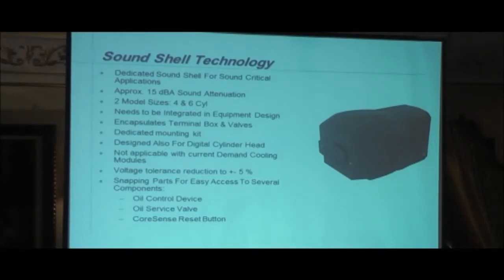Over and above that, we also offer now sound shell technology. It's basically a foam that's been molded, and that can be applied to fit around the compressor. So even with the redesign, we've had the reduction in noise. By using the sound shell, we're able to reduce the noise by another 10 to 15 dBA. So this is an option or an accessory that can be used if you have noise-sensitive applications.